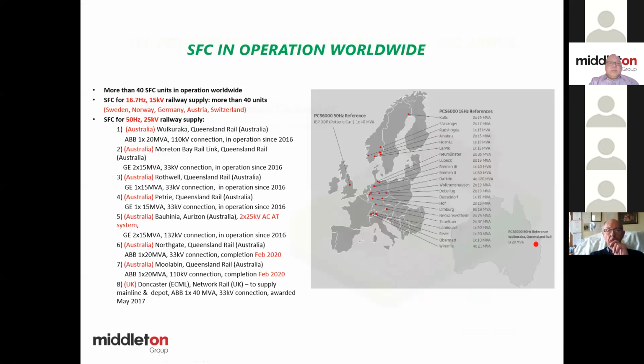So where have they been used? There are actually 7 units already installed in Queensland, Australia. 6 of them are rail return system, 1 times 25 kV. Only one of them, by Aurizon for the freight train, is 2 times 25 kV AC on the output. So on the continent across there, lots and lots of units have been installed, and they're all 16 and 2/3 hertz, 15 kV.